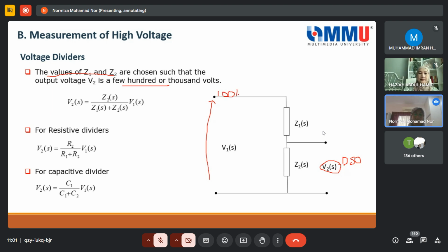100 kV. So you have to make sure that this V2 should be measured by 50 volts only. And then V1 depends. If you want to measure a maximum of 100 kV, then it's 100 kV. So you have to get the value of Z2 divided by Z1 plus Z2 into this equation, but give the value of V2 very small, that should be able to be measured by the oscilloscope. So how much is it? Like for example, 50. What would be this ratio?